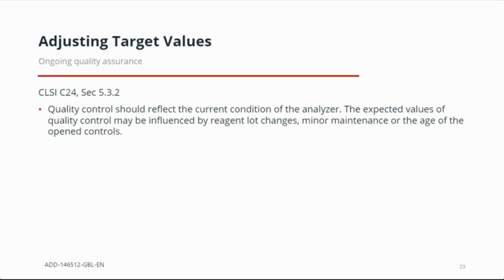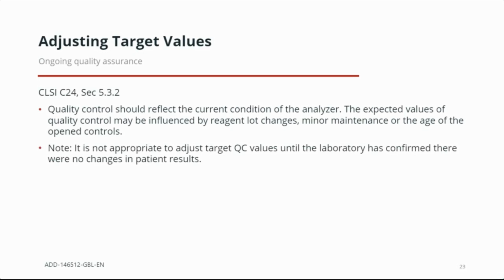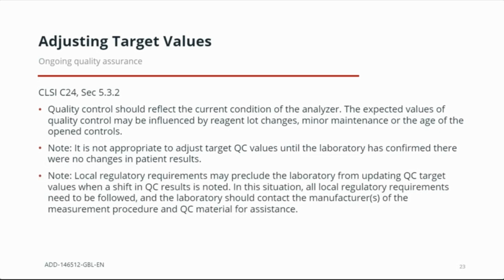CLSI C24 states that quality control material should reflect the current condition of the analyzer. The expected values of our QC material may be influenced by reagent lot changes, minor maintenance, or the age of open controls. It's important to note that the laboratory should not make adjustments to QC target values until they have confirmed there are no changes to patient results. So spot checking a few patient samples run before those reagent changes or maintenance changes would be one way to accomplish this. It's also important to note that local regulatory requirements may preclude the laboratory from updating QC target values when a shift in QC results is noted. So that adds a little bit of a challenge.